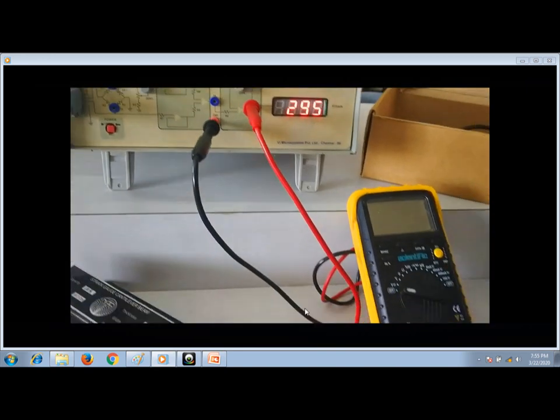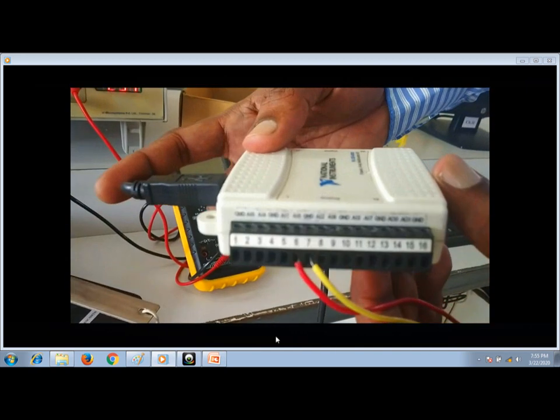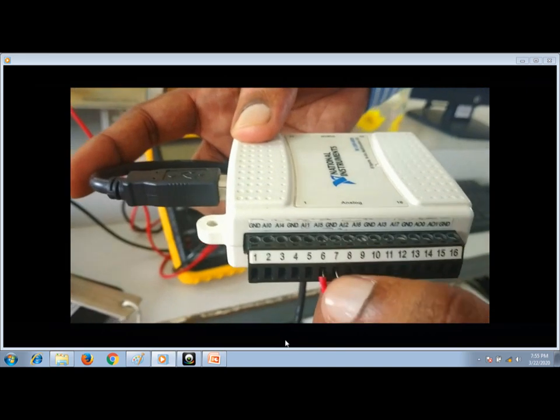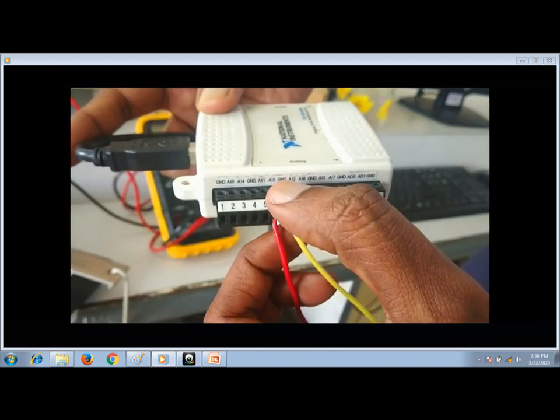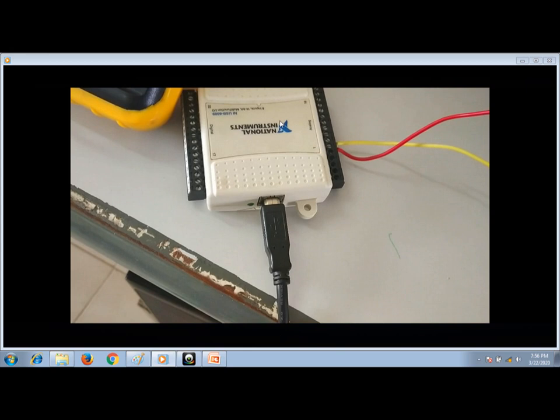We have the National Instruments data acquisition card. We are using the analog input channel — this is the positive output and this is the negative. We connect the 0 to 5 V output from the signal conditioner to this data acquisition card. The card converts the analog 0 to 5 V into a digital output. There are multiple analog input channels, and a multiplexer inside selects the appropriate channel through sampling.